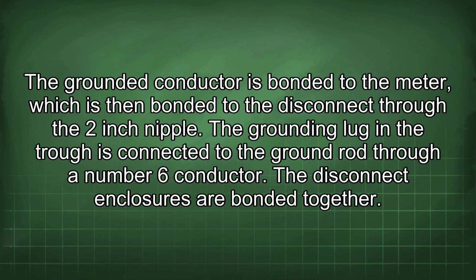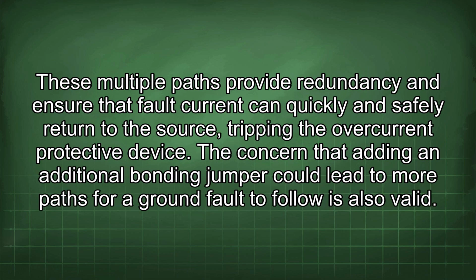The grounded conductor is bonded to the meter, which is then bonded to the disconnect through the 2-inch nipple. The grounding lug in the trough is connected to the ground rod through a number 6 conductor. The disconnect enclosures are bonded together. These multiple paths provide redundancy and ensure that fault current can quickly and safely return to the source, tripping the overcurrent protective device.